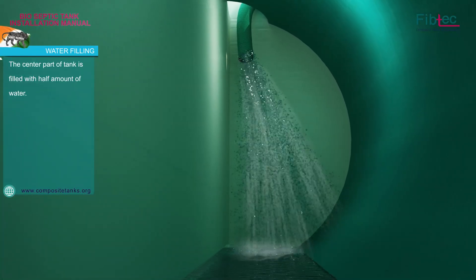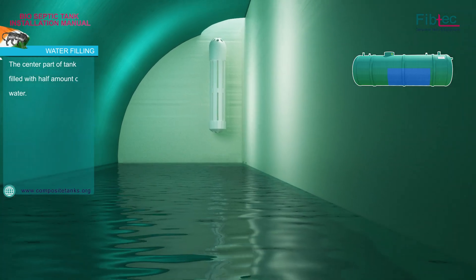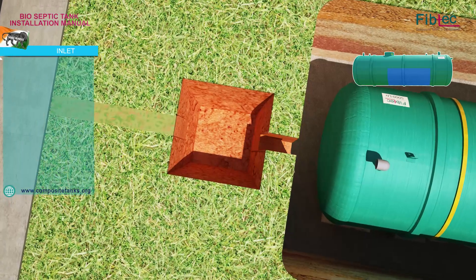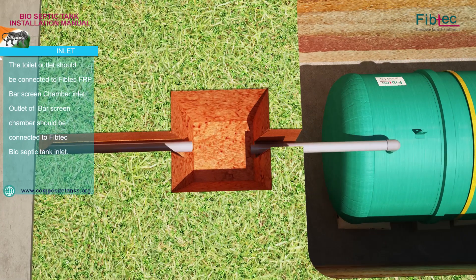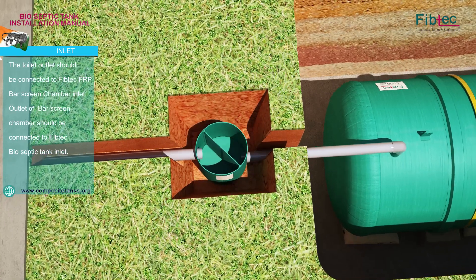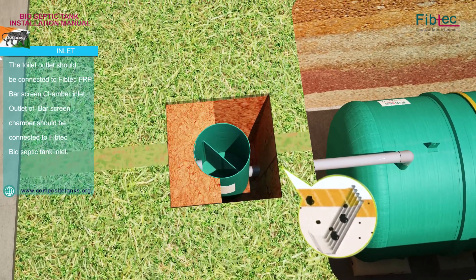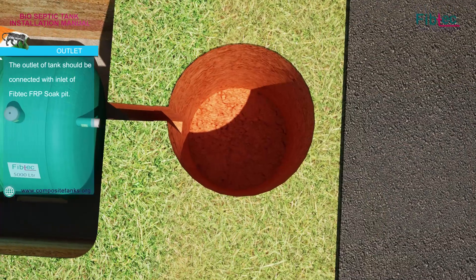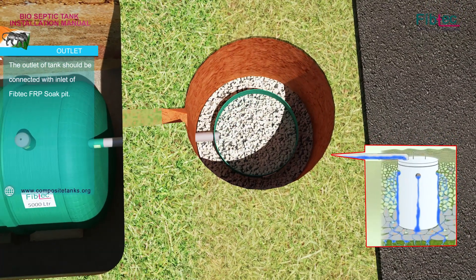The center part of the tank is filled with half an amount of water. The toilet outlet should be connected to the Fibtec FRP Bar Screen Chamber inlet. The outlet of the Bar Screen Chamber should be connected to the Fibtec Bio-Septic Tank inlet. The outlet of the tank should be fitted to the inlet of the Fibtec FRP Soak Pit.